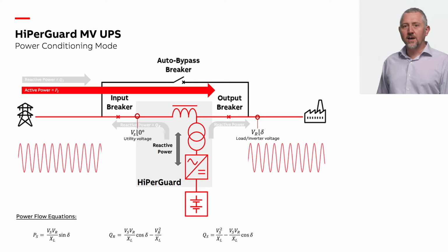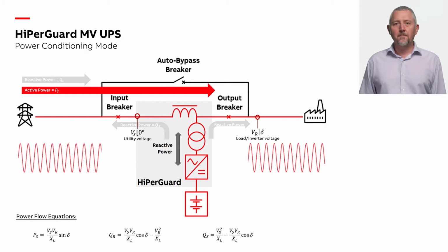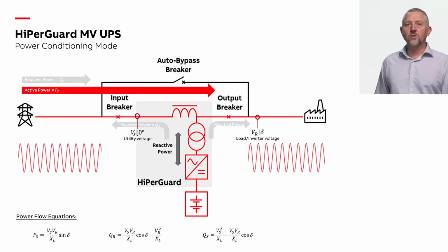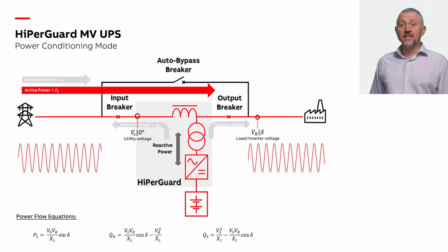In power conditioning mode, the HiPerGuard will inject or absorb reactive power into or from the load to keep the voltage at 100%. The HiPerGuard changes the angle between the grid and the output voltage to absorb or inject reactive power into the system. During this action, there is no significant energy storage cycling. During power conditioning mode, the main purpose of the UPS is to supply perfectly balanced 3-phase voltage to the load, whilst assuring that the load's active power requirements are provided by the utility. This is achieved by controlling the voltage angle across the reactor, making PS equal to the load's active power requirements. This assures you that no energy storage is used during this mode, and the energy is saved to be used when the utility is further out of specification.